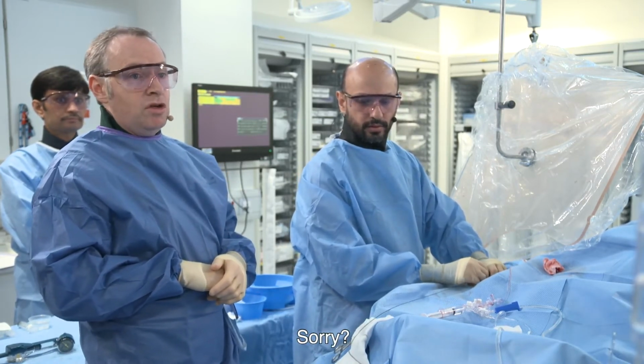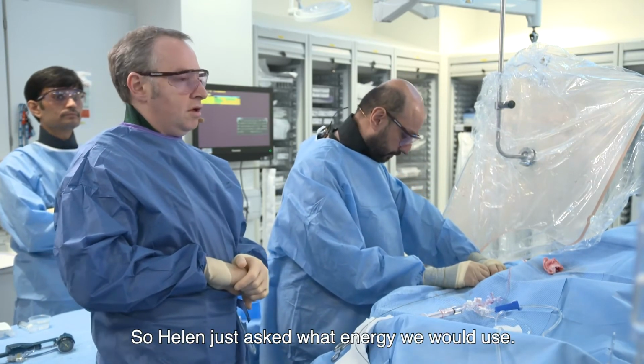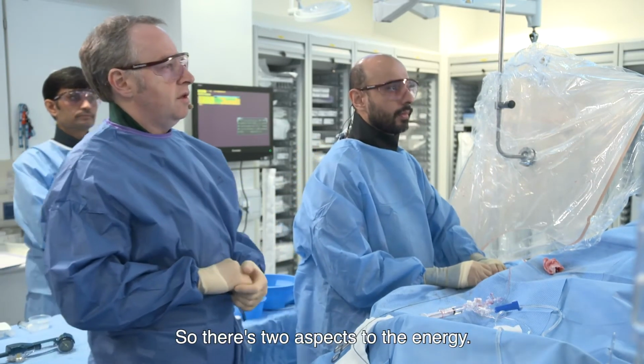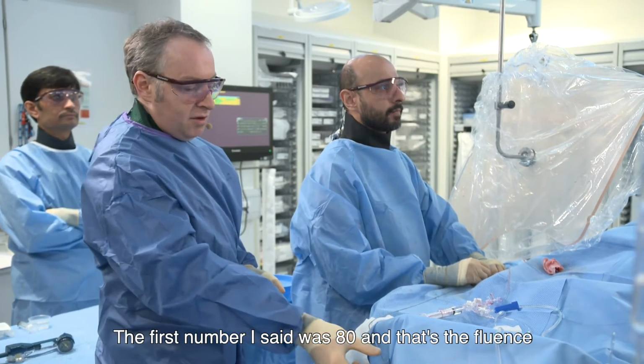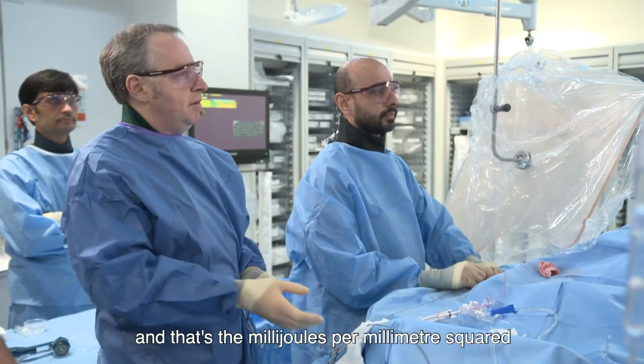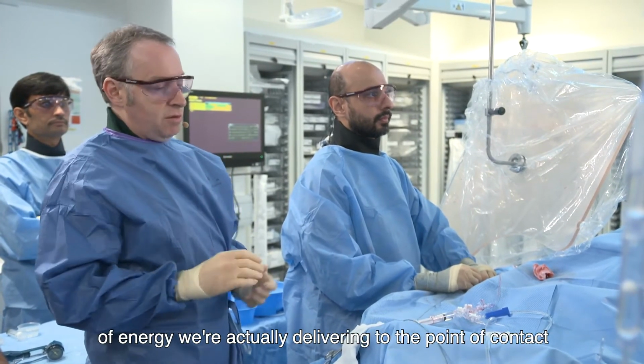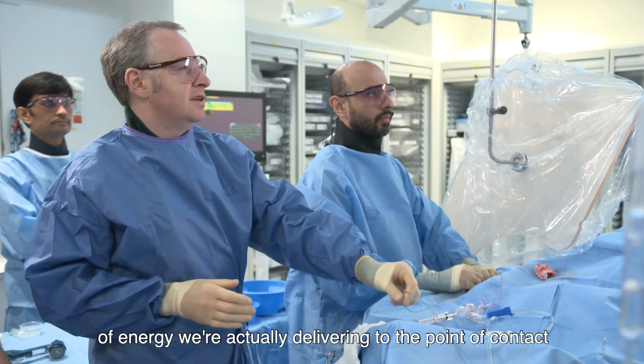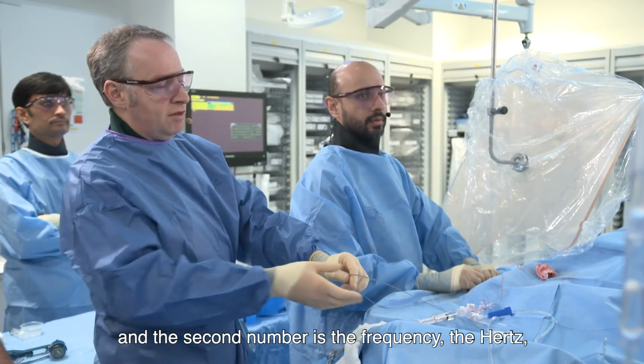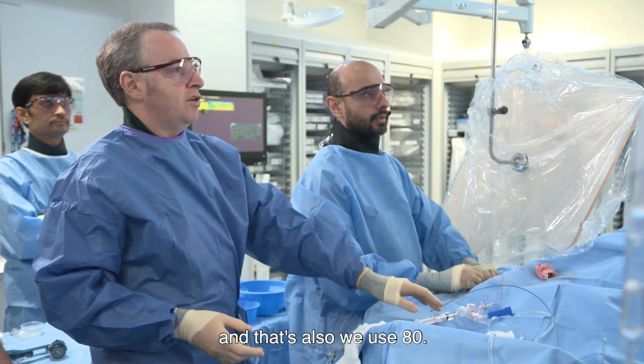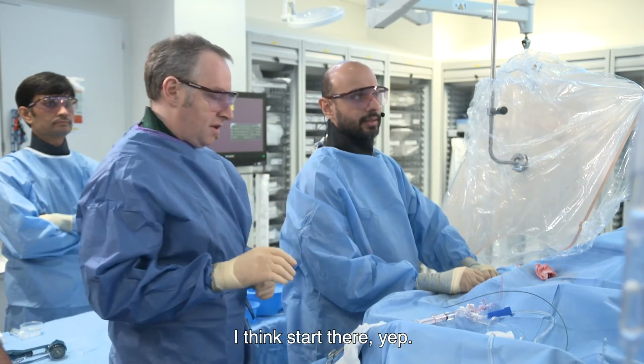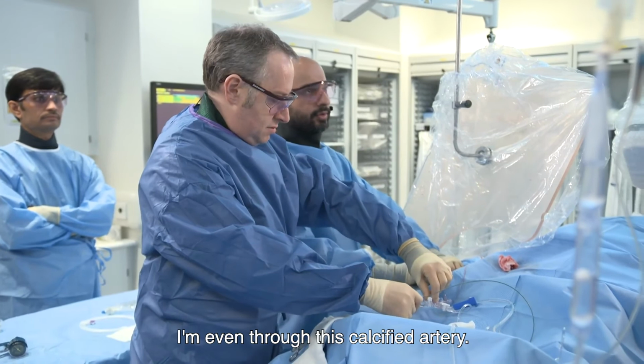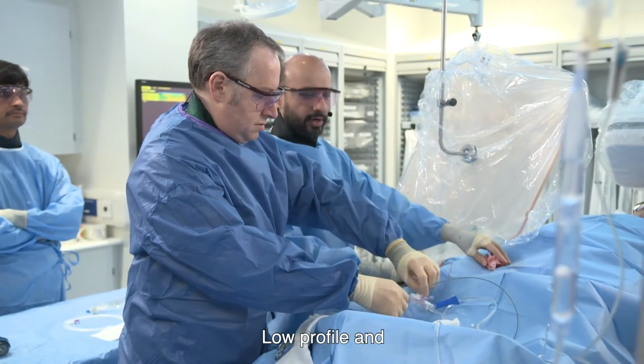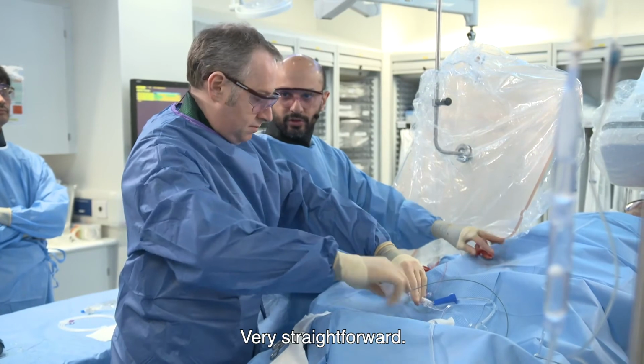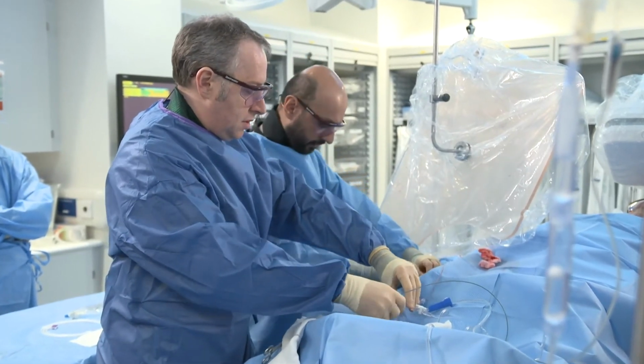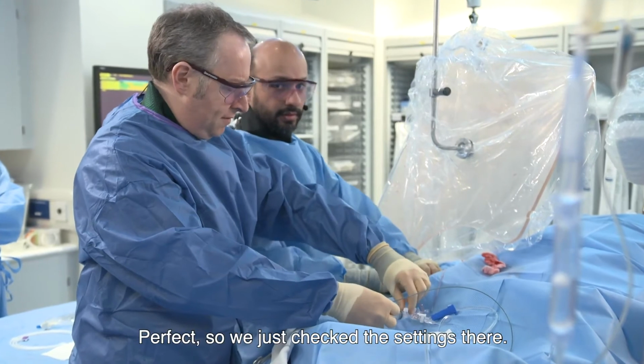Sorry. So we're going to go 80-80. So Helen just asked what energy we would use. There are two aspects to the energy. The first number I said was 80, and that's the fluence, the millijoules per millimeter squared of energy we're actually delivering to the point of contact. And the second number is the frequency, the hertz. And that's also 80. We start from about there, I think. So you can see it's very deliverable, even through this calcified artery, low profile, and you can put it through a 6 French guide liner. Very straightforward. So yeah, 80-80. Perfect. So we just check the settings there.